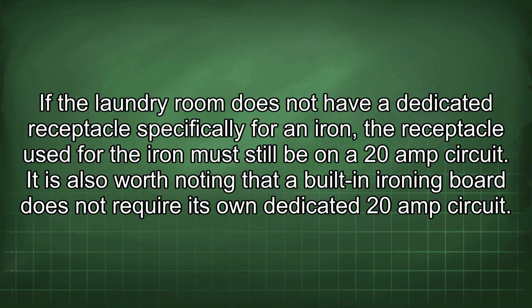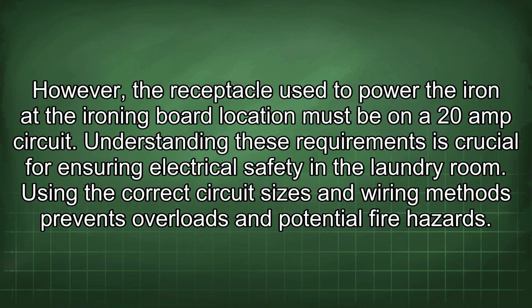If the laundry room does not have a dedicated receptacle specifically for an iron, the receptacle used for the iron must still be on a 20-amp circuit. It is also worth noting that a built-in ironing board does not require its own dedicated 20-amp circuit. However, the receptacle used to power the iron at the ironing board location must be on a 20-amp circuit.